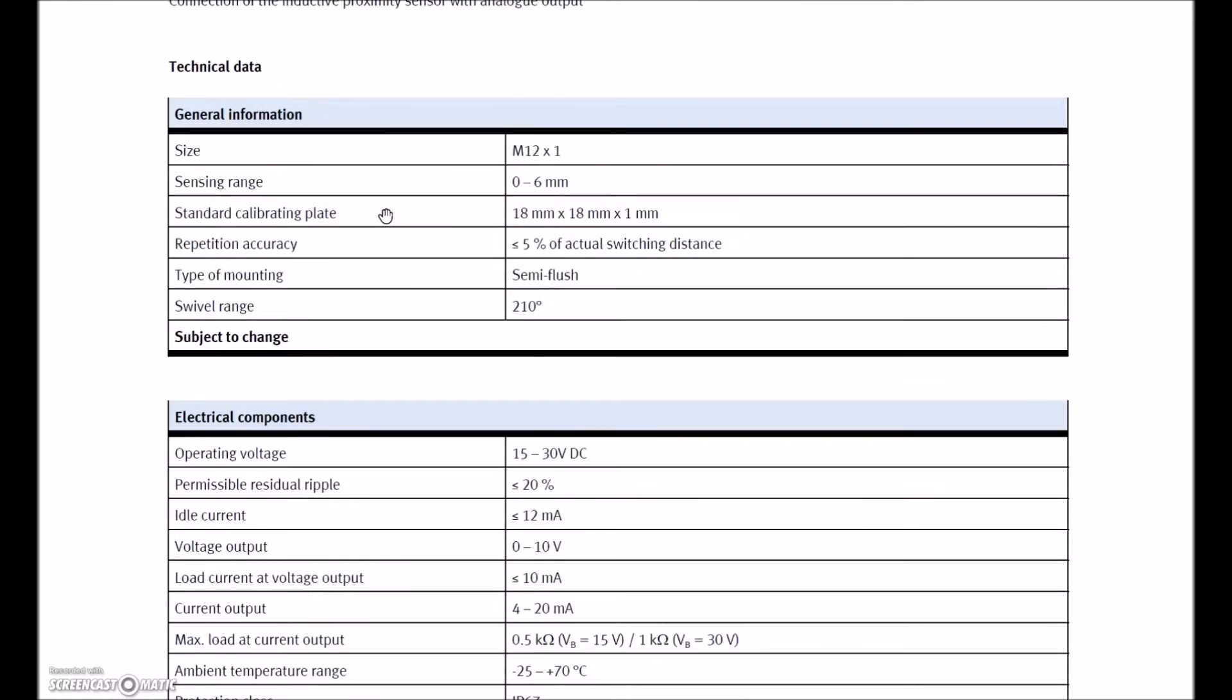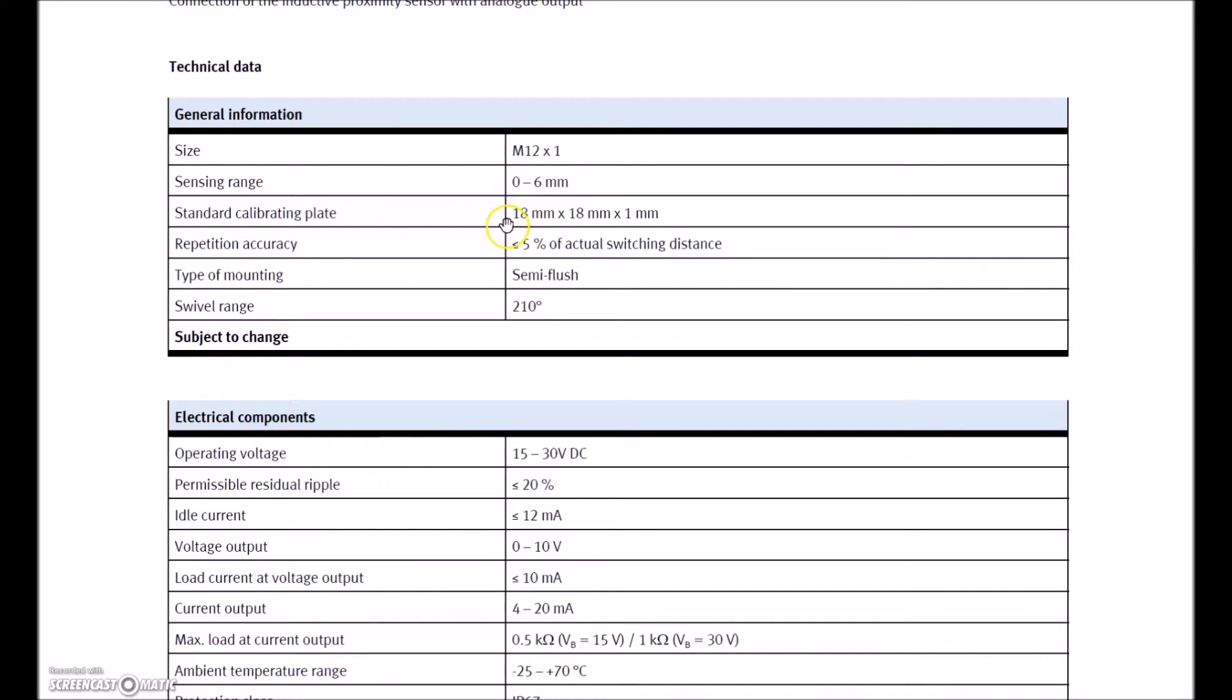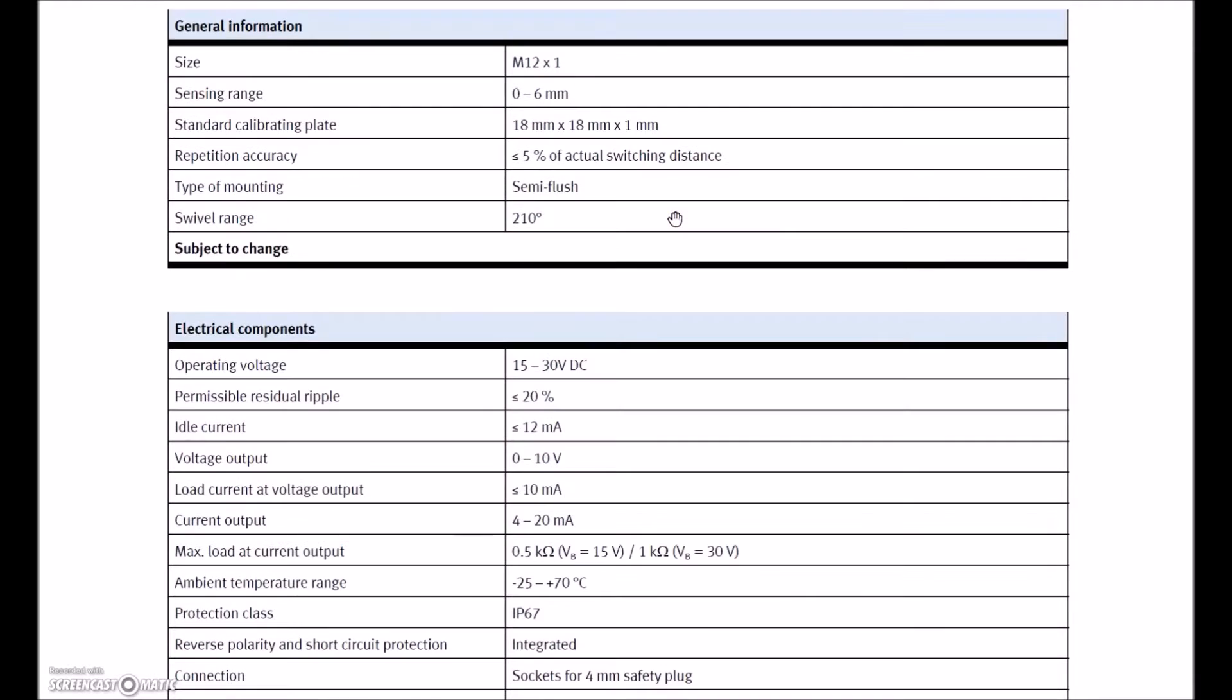Each of these guys has its own cut sheets. This is a little bit different than the other M12. It looks like the sensing distance is the same, 6 mm. Standard calibrating plate is exactly the same. Operating voltage is 24 volts DC. Idle current is 12 milliamps, so even when it's off, it's going to be pulling current.